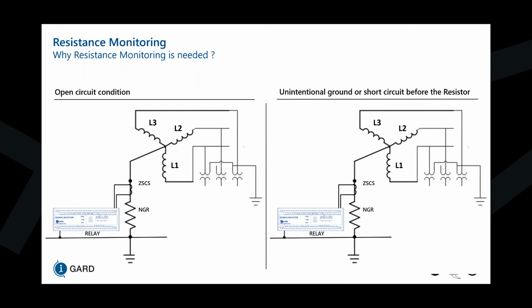Now in the past, and also in the US, because they don't have an open and short circuit requirement for monitoring the resistor, they would typically utilize a ground fault relay with a CT connected at the neutral to examine how much current is flowing through the NGR so that they can pick up their ground faults. But in the case of an open circuit condition here, this CT is essentially blind to the fact that they've just lost their system ground, and this entire system is now floating. This will impact your protection schemes downstream that may not work with an ungrounded system.